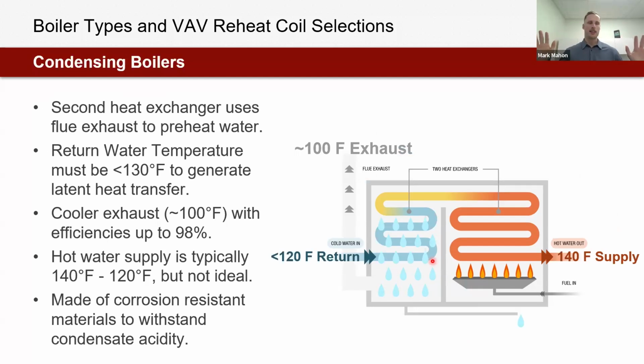Now, this is one of my biggest flagged takeaways. Please don't do that. I want to talk about why, but please don't do 140, 120. And the reason why we don't want to do that is because of the way a condensing boiler actually works to improve its efficiency. What we're doing is we're forcing the condensation as much as possible. We want this boiler to condense.